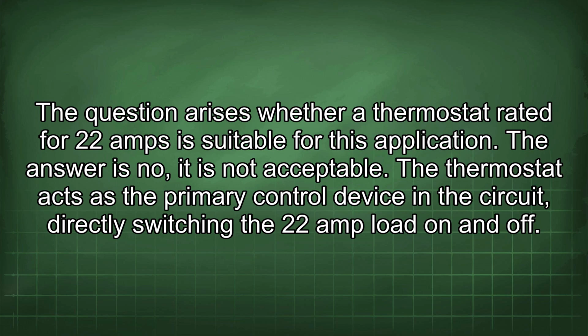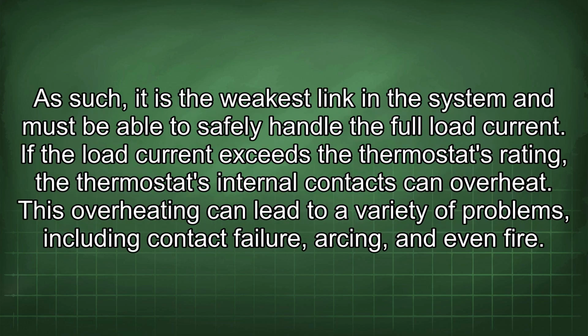The thermostat acts as the primary control device in the circuit, directly switching the 22 amp load on and off. As such, it is the weakest link in the system and must be able to safely handle the full load current. If the load current exceeds the thermostat's rating, the thermostat's internal contacts can overheat. This overheating can lead to a variety of problems, including contact failure, arcing, and even fire.